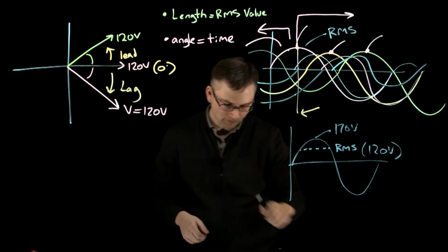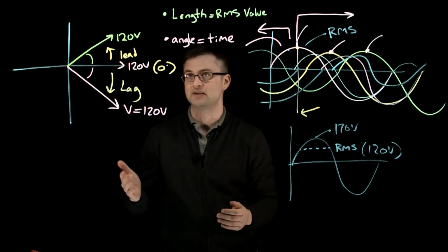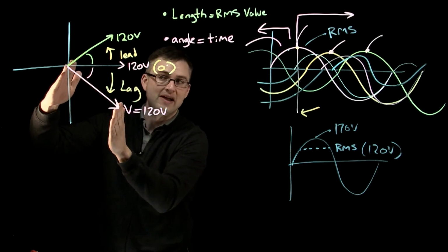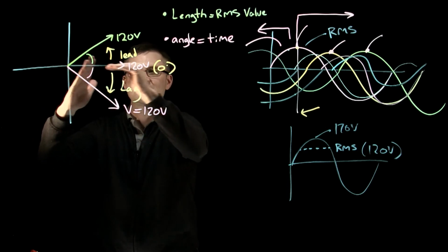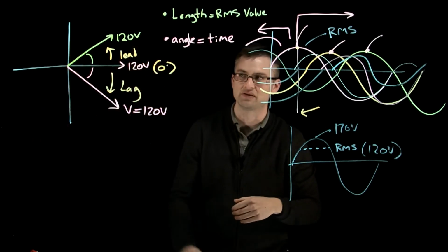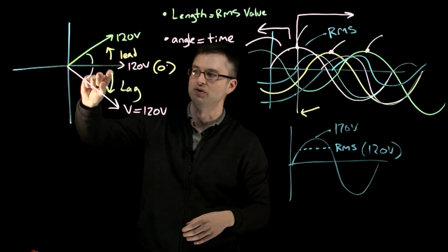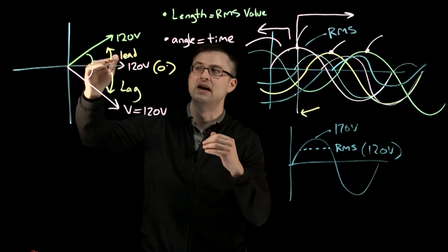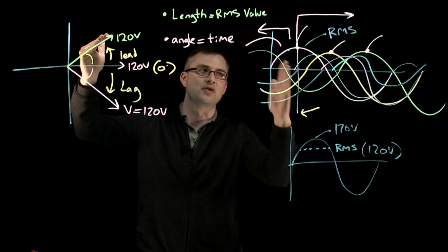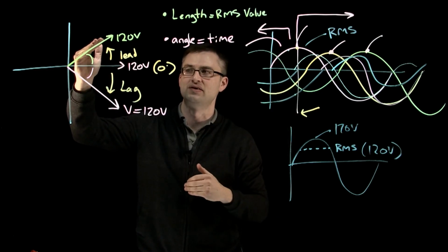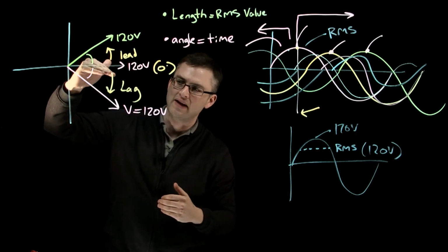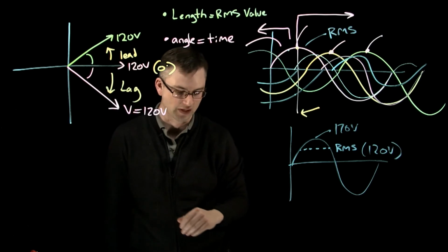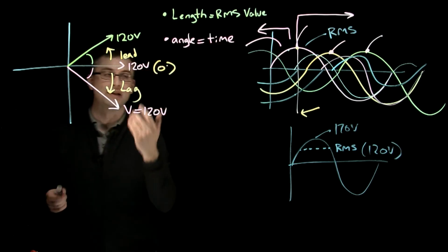Okay, so that is what's going on with a phasor. It is a magnitude measured in RMS, and it's the time in which it happens compared to that reference. In this I've got 3 different voltages. I've picked my reference in the middle at 0 degrees. I've got one that's a little bit ahead, so it already happened by the time I got to my reference peak. And this one lags behind, meaning it happens after my reference peak in my sine wave. I've only got 3 on here.